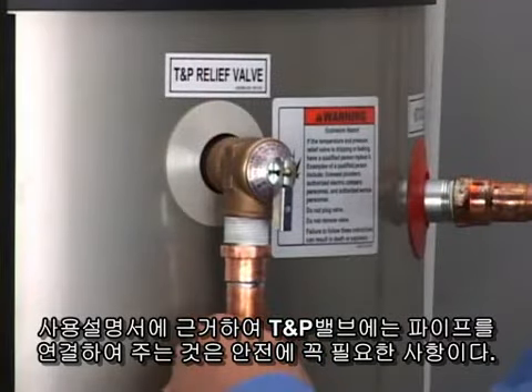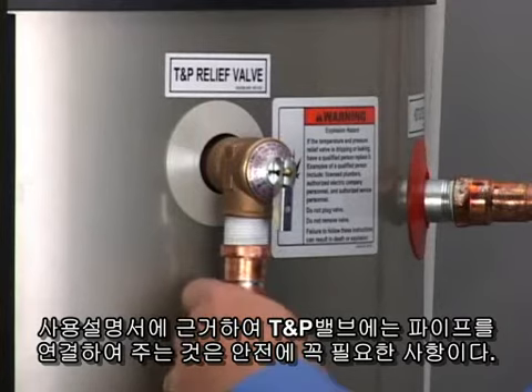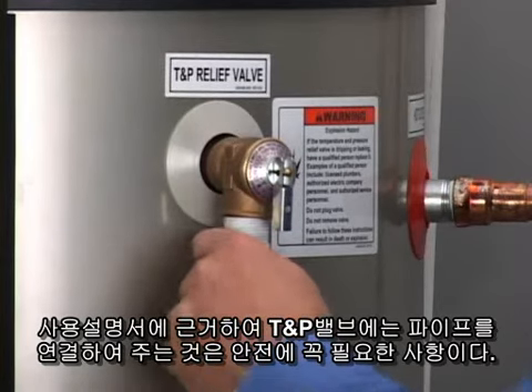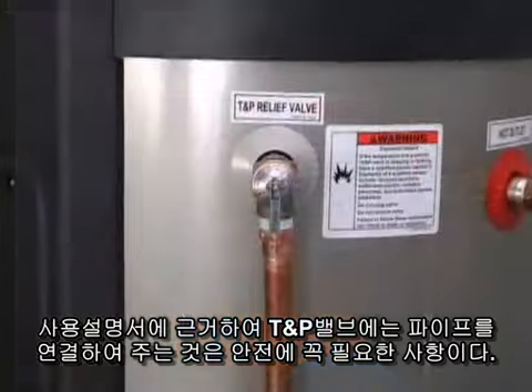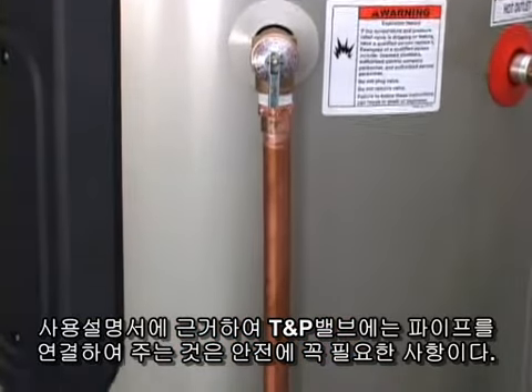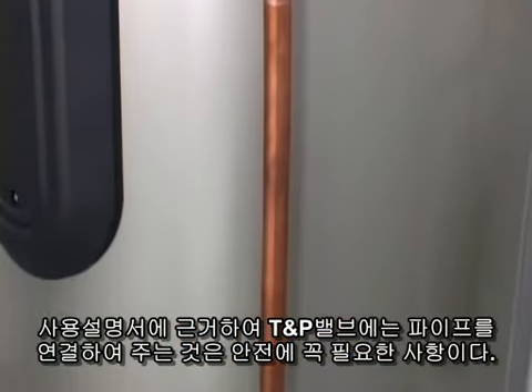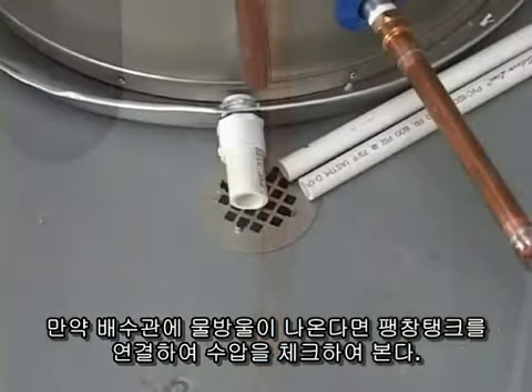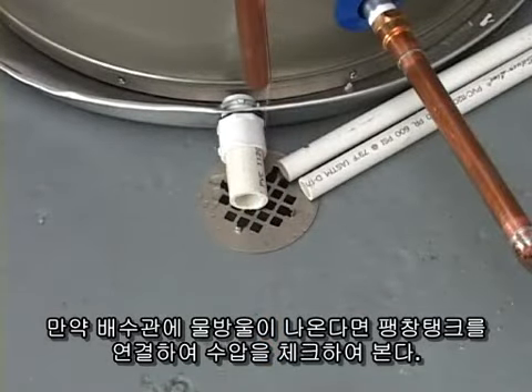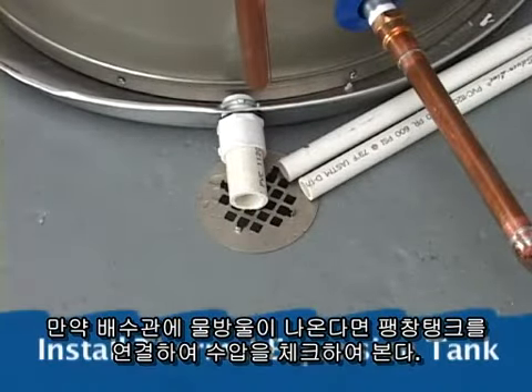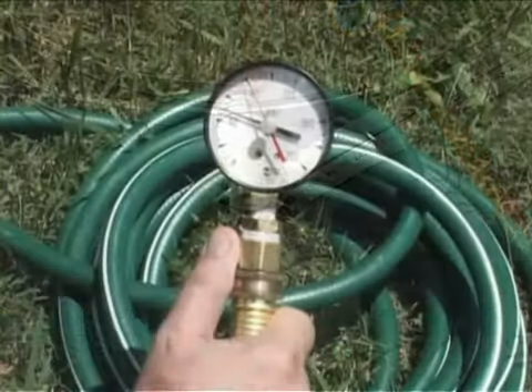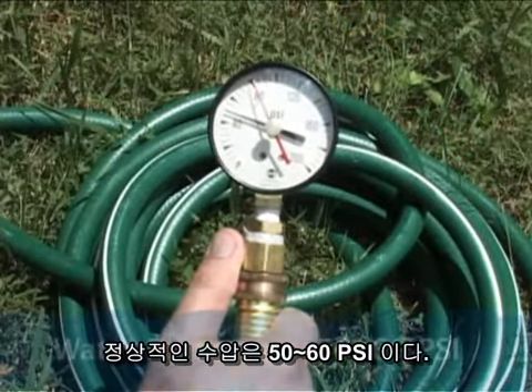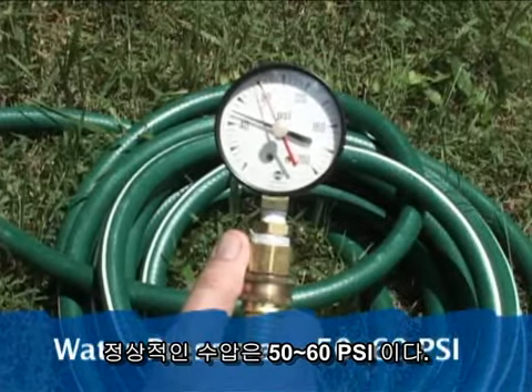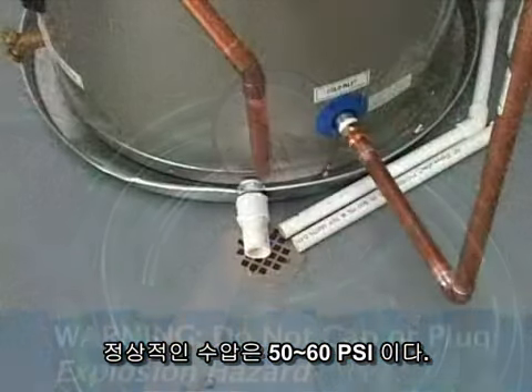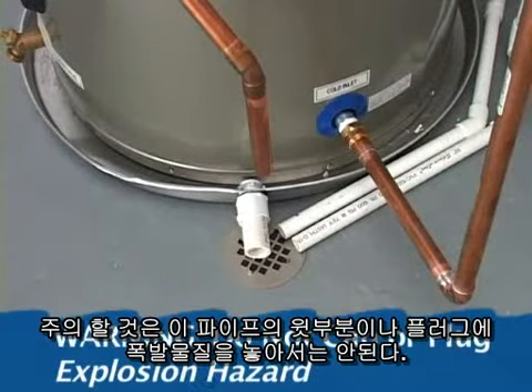Attach the discharge pipe to the water heater according to the installation instructions. This pipe is attached to the temperature and pressure relief valve, which is an important safety device. If the temperature and pressure relief valve drips, install a thermal expansion tank and check your home's water pressure. The correct pressure should be between 50 and 60 pounds per square inch. Do not cap or plug the discharge pipe.